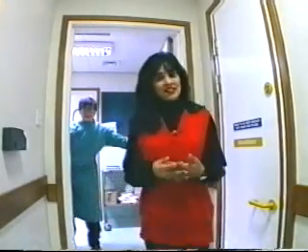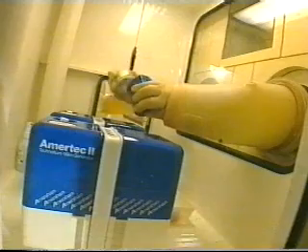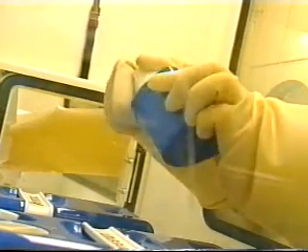The blue box is called a technetium generator. This is because most of the molybdenum-99 inside will, over the next few days, decay into technetium-99m — and that's what we need for our imaging. Molybdenum-99 has a half-life of 66.7 hours, so a fresh generator arrives at the hospital every week, thereby ensuring a steady supply of technetium. The radiopharmacy's task each morning is to extract the technetium produced during the previous 24 hours.